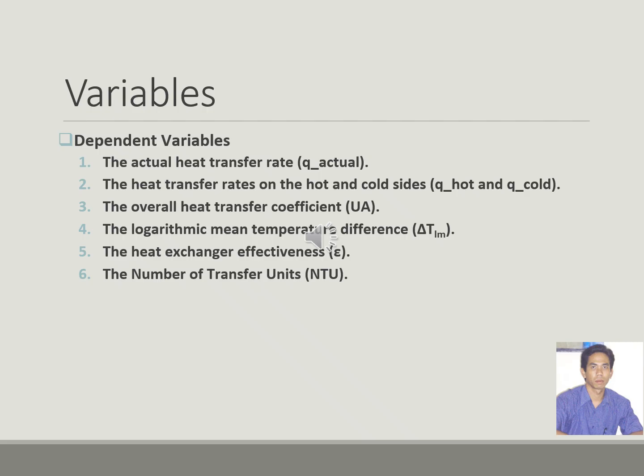The heat exchanger effectiveness is defined as the ratio of actual heat transfer to the maximum possible heat transfer, making it a key indicator of system performance. And finally, the number of transfer units is a dimensionless parameter that describes the heat transfer capacity relative to the thermal capacity of the fluids.